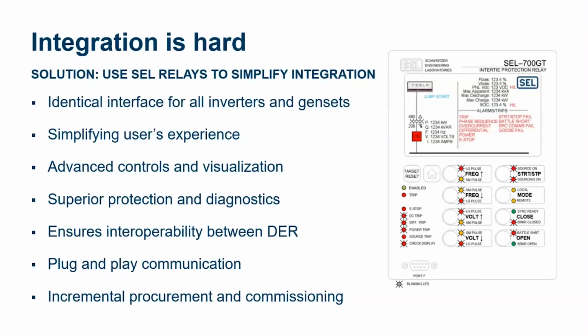We consolidate multiple pieces of equipment into a single relay. That's a complexity reset. We simplify the user's experience. Instead of a technician or engineer having to understand how to log in with multiple softwares, with multiple laptops, with multiple interfaces to different inverters and generators and battery management systems, you get a top-level display on a relay. The same relay that your utility partners have used for decades. So utilities love to see the solution. Look at how simple it is. Everywhere you go, for every photovoltaic, for every wind, for every battery system, it's the same buttons in the same location. It reduces error. It reduces training costs. It reduces complexity. It's a large value add.